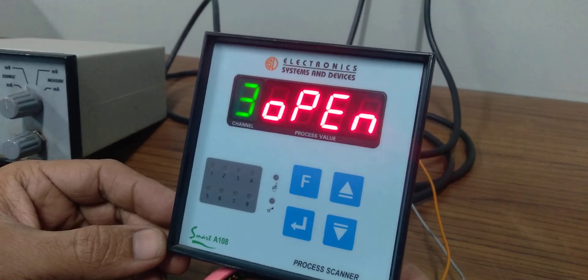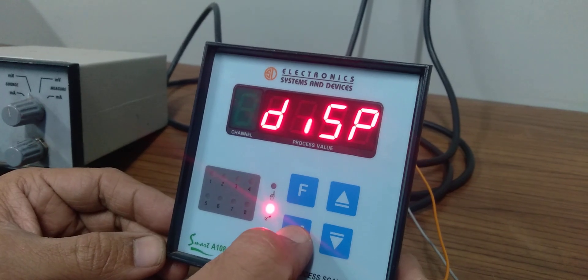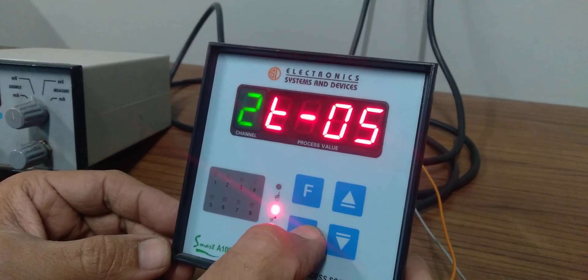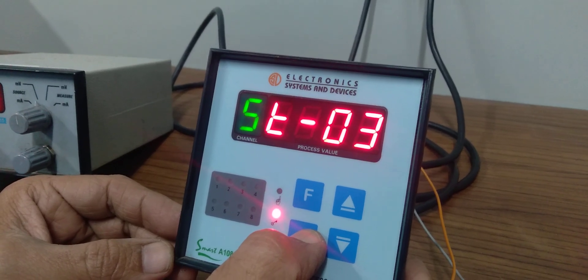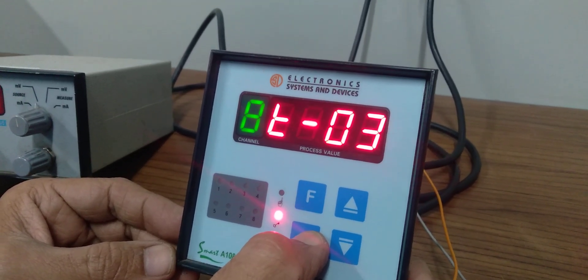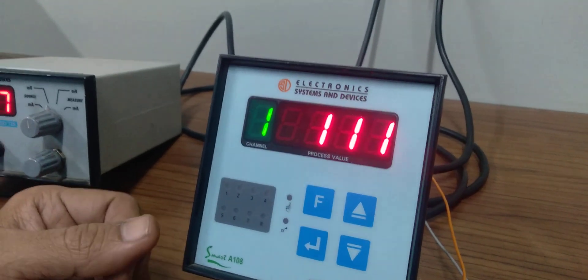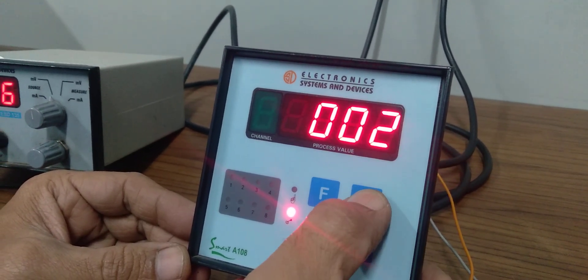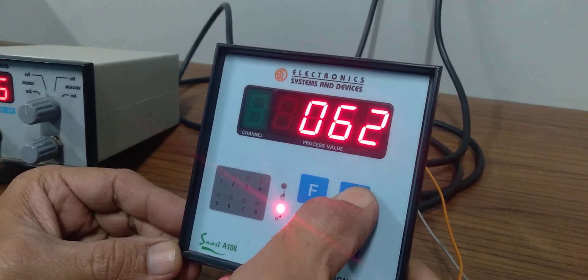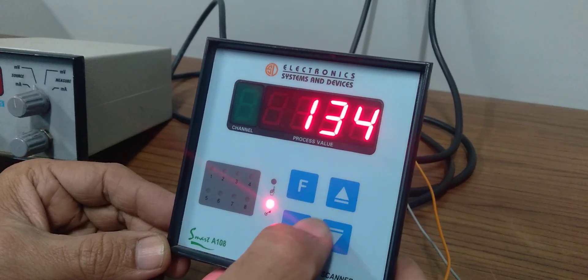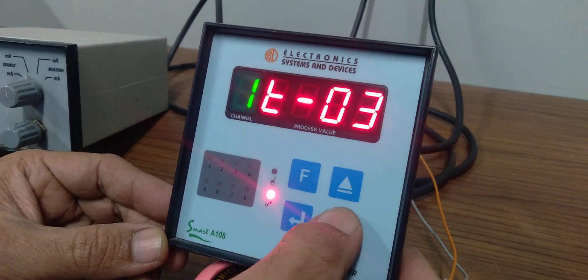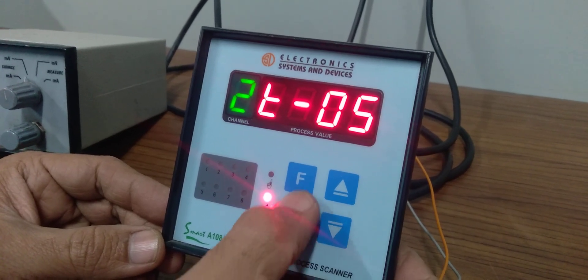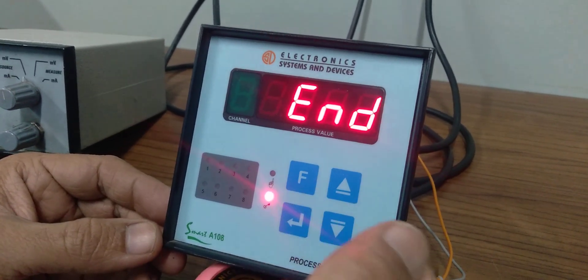We'll see the display times now. In the display option, you can set the time for each channel, how many seconds it should show. The minimum is three seconds. If you want to skip any particular channel, you can set it to zero. The default password is 134. We'll skip channel one. After entering the password and setting it to zero, press enter, and this particular channel will get skipped. Now it will start from channel two directly.